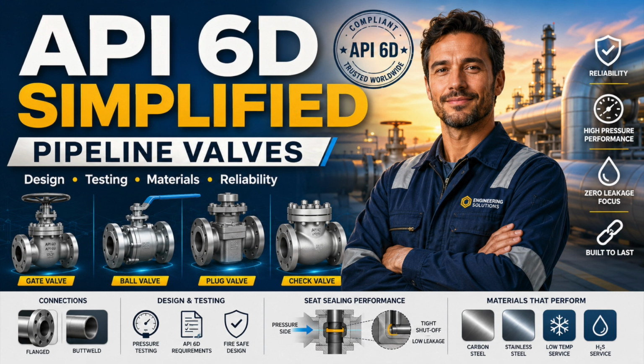The valve ends are another underestimated design boundary. For flanged valves, facing type, dimensions, drilling, finish, and compatibility must be correct. For butt-welded valves, the engineering becomes more critical. The valve end must match the pipeline. You need the correct nominal size, wall thickness, bore, material grade, specified minimum yield strength, and transition geometry. A poor weld end transition can create local stress concentration. It can complicate welding. It can obstruct pigging. It can create internal mismatch. It can create non-destructive examination difficulties. It can create a field problem that no amount of factory quality control can solve later. The valve to pipeline weld is not a minor fabrication detail. It is a system interface.